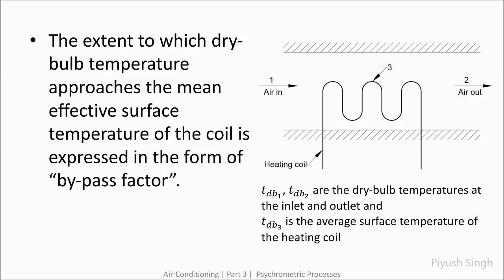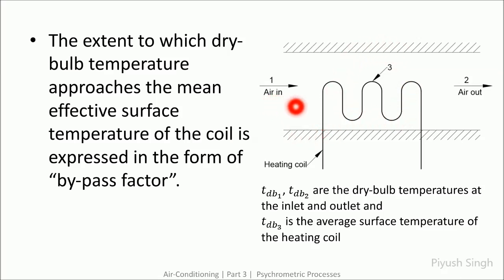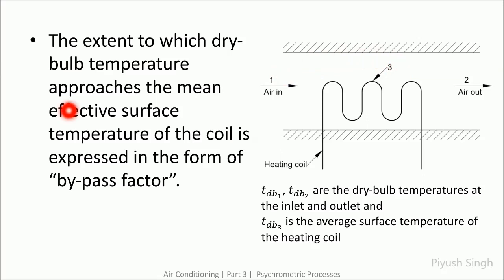The incoming air is at condition 1, the outlet condition is 2, and the coil surface temperature is at condition 3. Ideally, the air will come in contact with the coil and should reach the coil surface temperature. But in practice this is not observed, and the outlet temperature is somewhat between conditions 1 and 3.